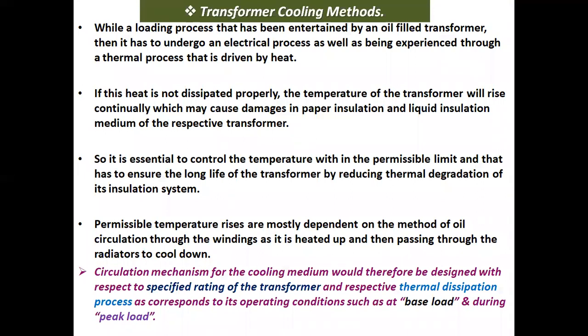Transformer cooling methods. While a loading process is undertaken by an oil-filled transformer, it has to undergo an electrical process as well as a thermal process that is driven by heat. If this heat is not dissipated properly, the temperature of the transformer will rise continually, which may cause damage in paper insulation and liquid insulation medium of the transformer. So it's essential to control the temperature within the permissible limit, and that has to ensure the long life of the transformer by reducing thermal degradation of the insulation system.